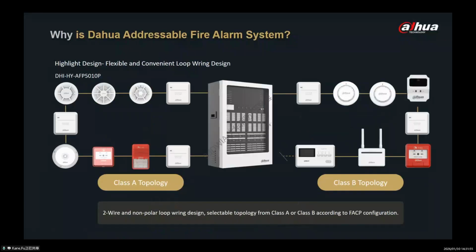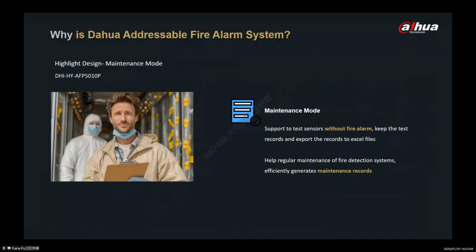It is the ring topology here, supports both class A and class B. And also it supports the maintenance mode, to help you maintain the system. In this mode, it will also report the alarm event, but will not link any real alarm and trigger the alarm device.